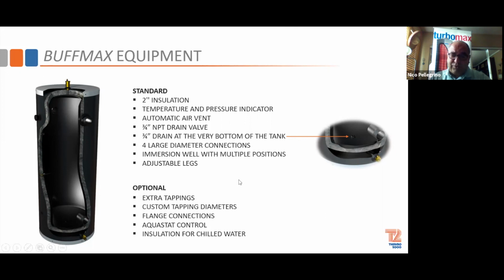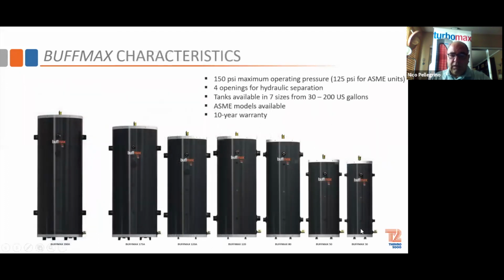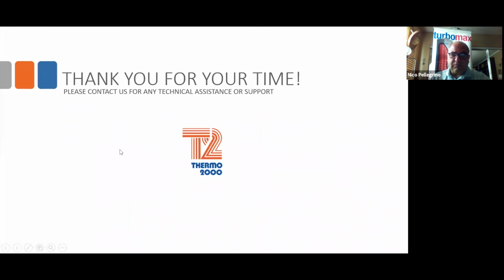There are some options that you can get. You can get extra tappings on the tank. The geothermal guys and the wood burning guys like it, so they can stratify the tank. We can also give you different tapping diameters. We also have flange connections. There's aquastat control we can give you. And this tank has an option to be with insulation for chilled water. It goes from 30 all the way up to 200 ASME. 10-year warranty on the tank. That's it.